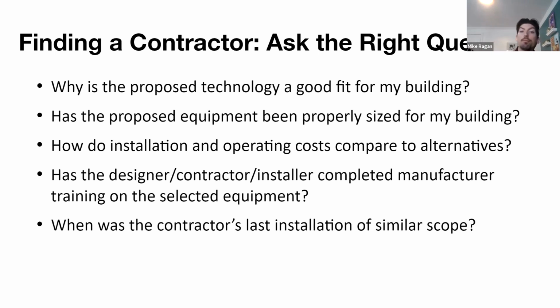How do install and operating costs compare to alternatives? The reality is this equipment, VRF and heat pump equipment, is installed with copper piping. Copper piping, there's certainly a premium on it. So you want to ask the question about total cost of installation. And when it comes to total cost of installation, don't let sticker price just shock you. Also consider your operating costs. Consider the efficiency gains you're going to be getting with this system.